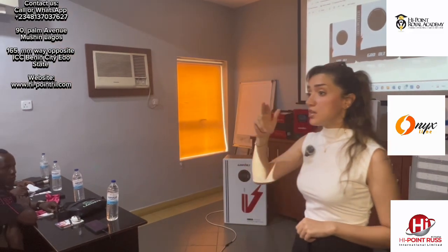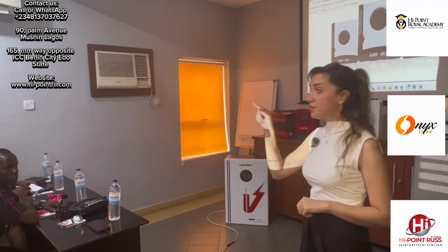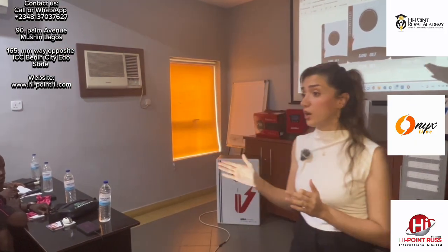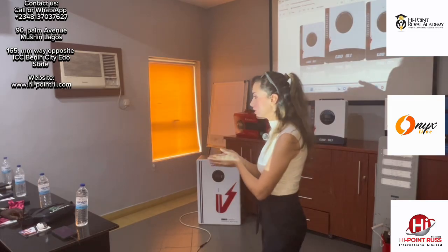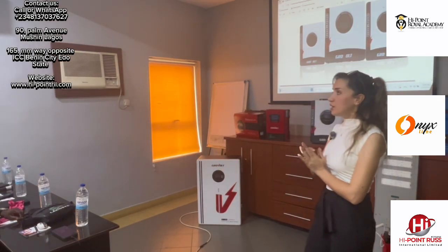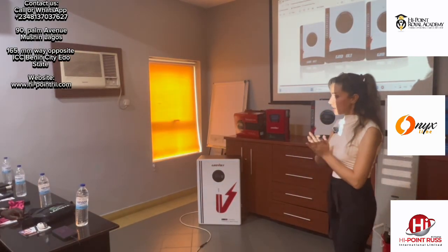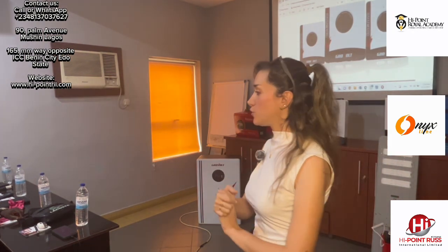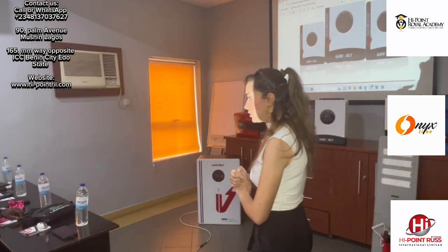In addition, the voltage for the MPPT range is 500 volt. So 500 volt, if we calculate for a panel of 550 watt, and the VOC for this panel is 45 volt.